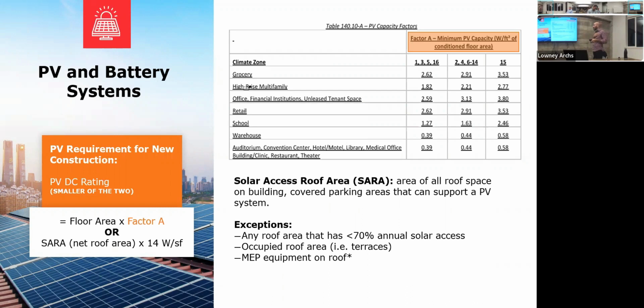The second formula is based on the net roof area available on your project. So you take your net roof area and multiply it by 14, and then again you come up with another number in watts, and that's also PV capacity. You take the minimum of the two, and that's your PV requirement. I'll show you an example. In terms of this net roof area, for multi-story buildings usually the second formula will give you the lower number, and that will be your requirement for the code.